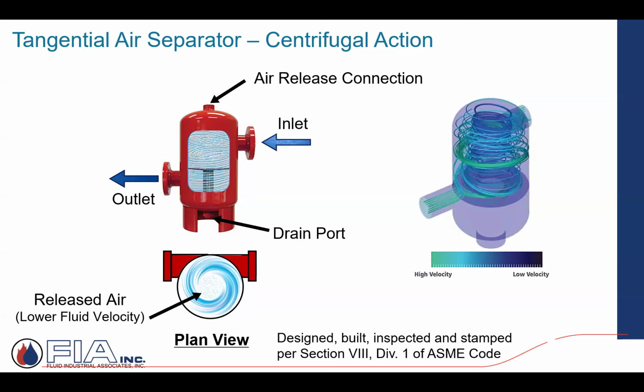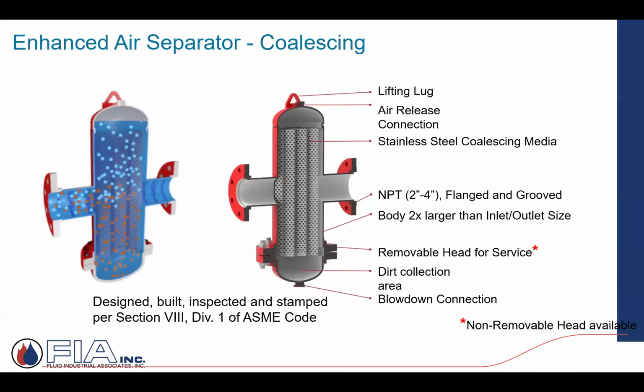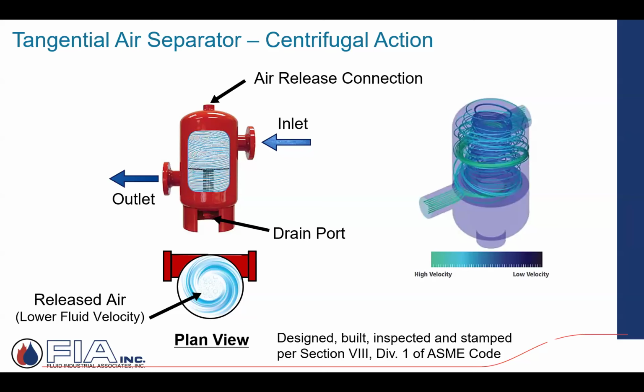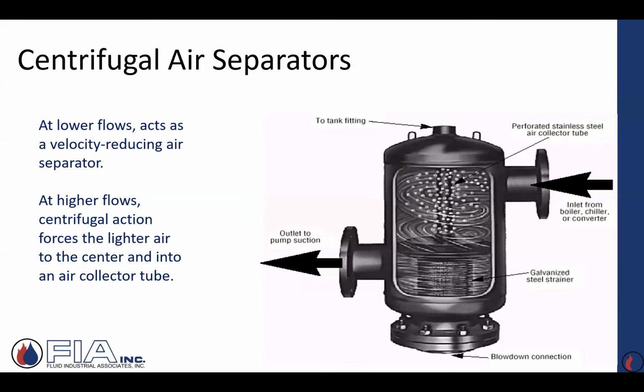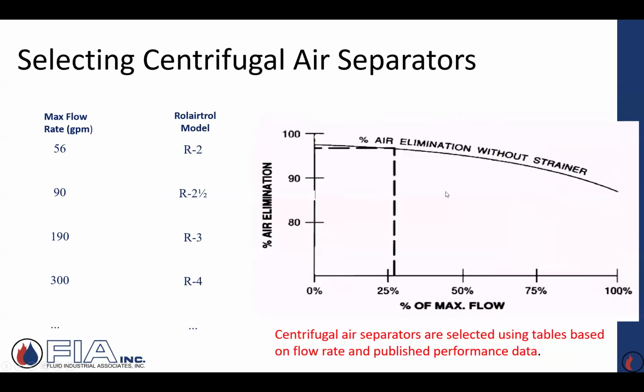So this technology, very effective, very common in a commercial space. So either I'm doing coalescing, one of these guys in a commercial setting, or I'm going to go with this Rolairtrol, this centrifugal action as my air separator. Both of them are effective. Lower flows act as a velocity reducer. As you get into your design flows, your higher flows, it's that centrifugal action that takes over to allow the air to separate and gather in the center of this shell, if you will, attached to this stainless steel collector. Then we've got some spec sheets. They've got some submittals where they talk about the amount of air that's separated per pass. It's quite effective.